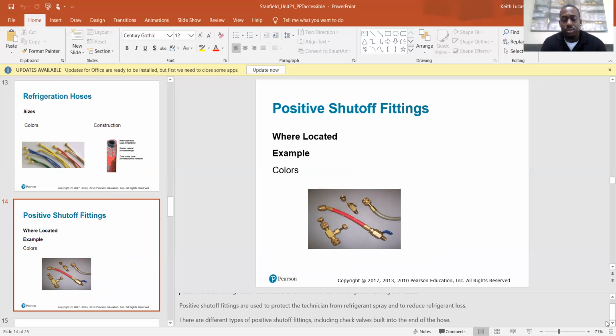So when you're taking your hoses off of a system, you don't have to worry about so much of that spray that comes out and freezes your fingertips and wastes your refrigerant. You still might get a quick little psst, but it's a lot less. And a lot of times people start panicking once that starts flowing out, and then they freeze up. And I always tell people, don't do that. If you freeze up, you're gonna stand there and wait until the entire system is flat, and you just release all the refrigerant out of it.